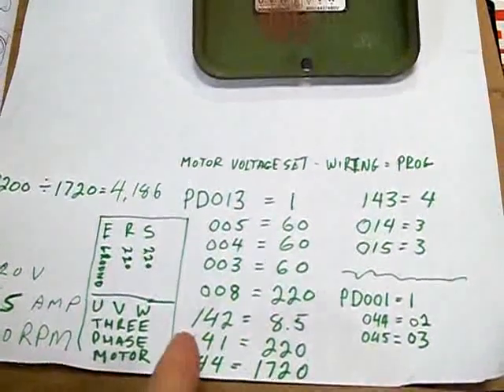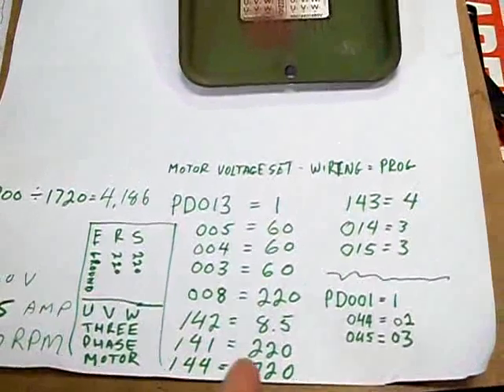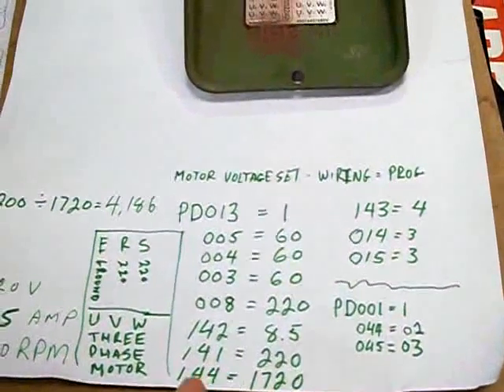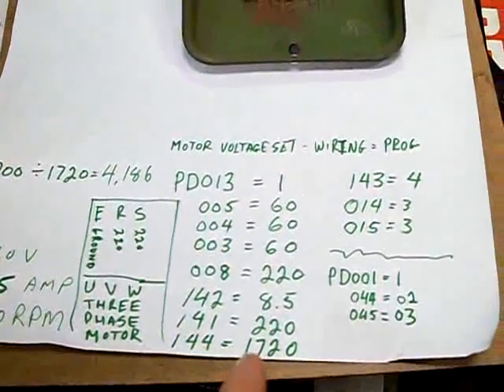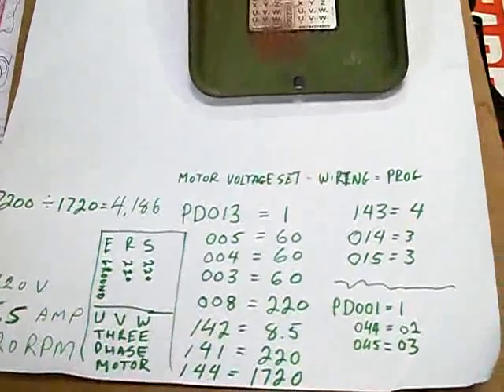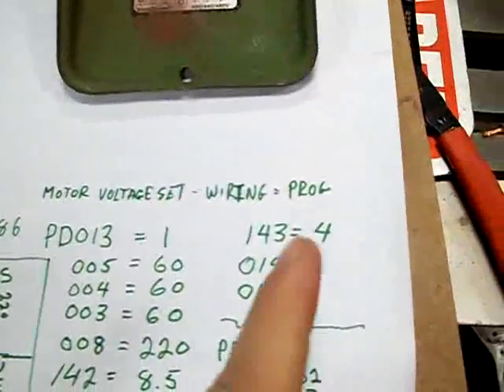220 was the max voltage. 142, that was the amperage on the motor, 8.5 amps. 141 was the voltage on the motor. 144, 1720 RPMs. And 143, that's the number of poles.